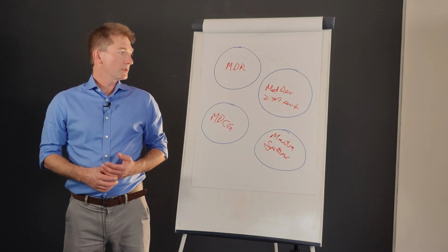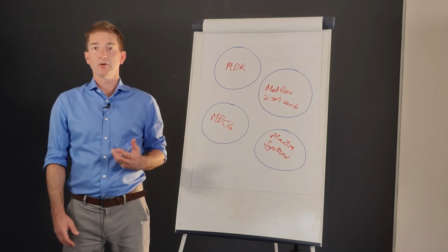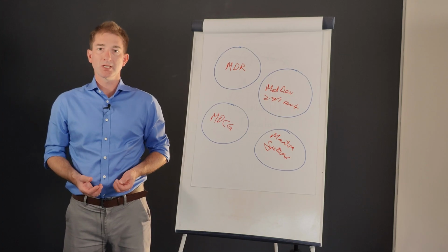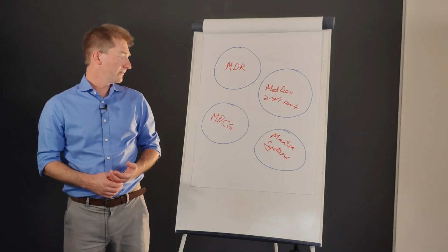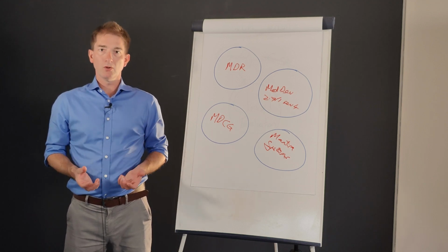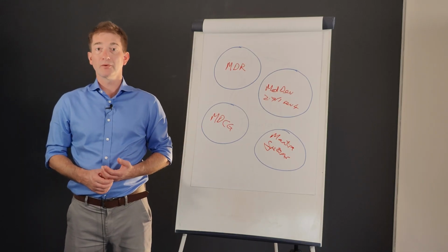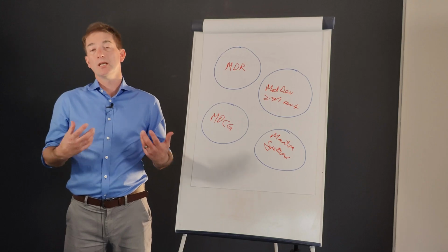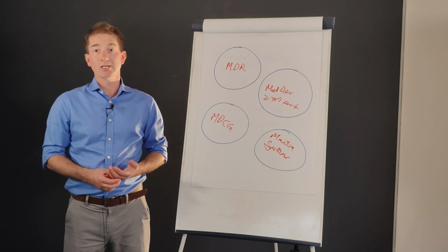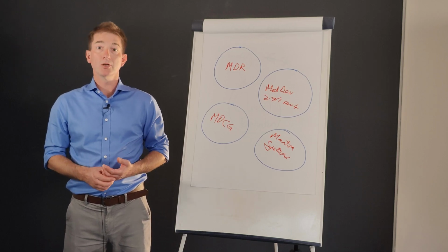MEDDEV guideline 2.7/1 revision 4, bit of a mouthful. This was the old go-to guidance for clinical evaluation under MDD. It is a little bit out of date now, but there are still some parts of it that can be considered, including structuring a search protocol. The MDCG guidelines are much more up to date. They're not actually law, but they're often taken almost as if they were. We mentioned 2020-5 before for equivalence. 2020-6 is specific information in relation to submissions for legacy devices. And 2020-13 is almost a cut-down mark scheme that notified bodies will look at when evaluating your clinical evaluation.